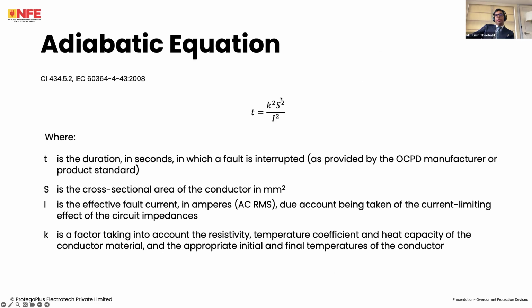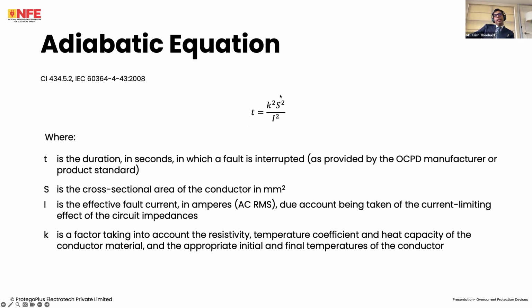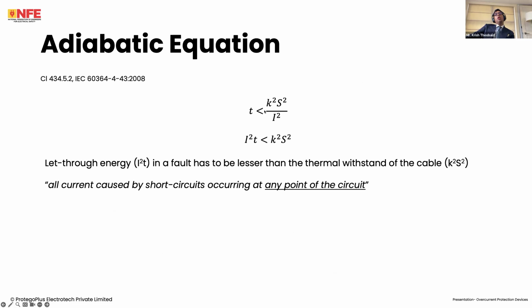S is the cross-sectional area in square millimeters. I is the fault current to be calculated based on this value. And K is, like I said, this factor. For faults that are interrupted within 0.1 seconds, which are current limiting devices generally, we can rearrange this equation: I squared T shall be less than or equal to K squared S squared.